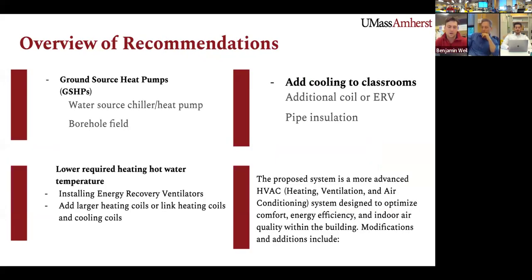So we analyzed all of the options to meet the town's goals, and we found the best one was a ground source heat pump. To use a ground source heat pump, you have to install a chiller and a borehole field. We have investigated and have suggested locations for the borehole fields. A goal is to add cooling to classrooms, and a ground source heat pump is an extremely efficient way to do that if coils or ERVs are installed. With added cooling, pipe insulation will be required to prevent condensation. In order to use a ground source heat pump, water temperature needs to be lowered by adding coils or ERVs.